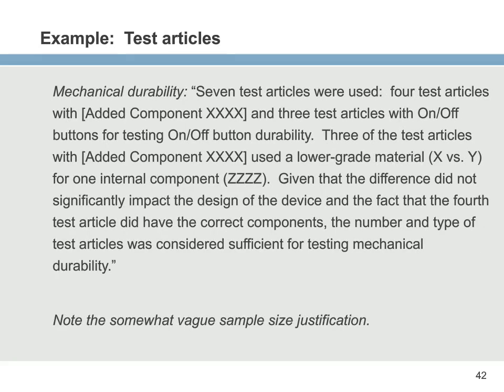Then here's a vague one, where we put sample size under test articles again. 7 were used, 4 articles had an added component, 3 articles had an on-off button for testing on-off durability. 3 of the articles had an added component using a lower grade of material for 1 internal component. I mean, it was messy, but it was all still legitimate, because given the differences that don't impact the design of the device and the fact that the 4th test article did have all the correct components, the number and type of test articles was considered sufficient for testing mechanical durability. So again, it's messy, it's complicated. You might as well explain it in the test summary, and it's completely reasonable.